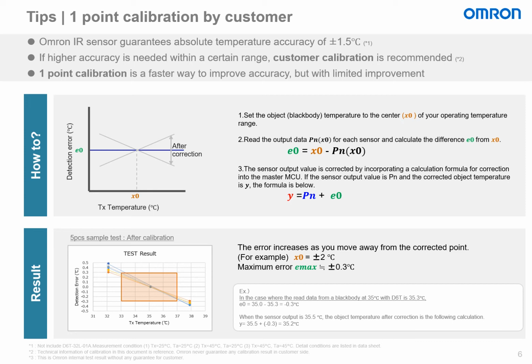Here we have the 1-point calibration method that the customer may also use. The 1-point calibration method is a faster way to improve accuracy, but with limited improvement. The method is similar. Set the blackbody object temperature to the center of your operating temperature range, or X0. Read the output data for each sensor and calculate the difference from X0. The sensor output value is corrected by incorporating a calculation formula for the correction into the master MCU. If the sensor output value is Pn and the corrected object temperature is Y, the formula is shown below.